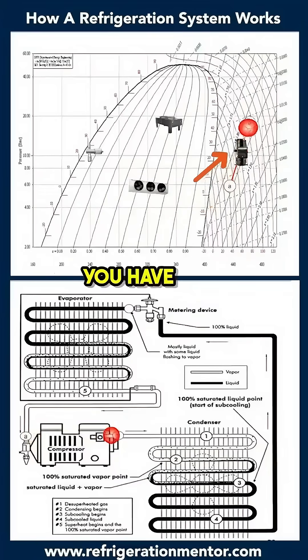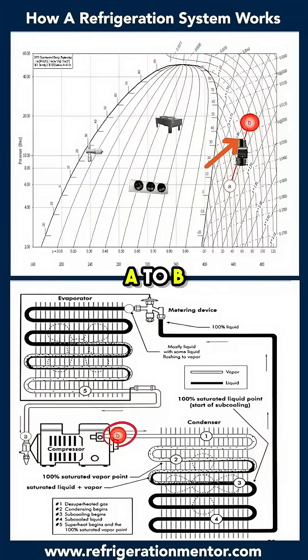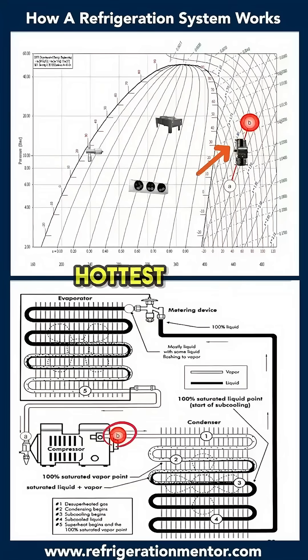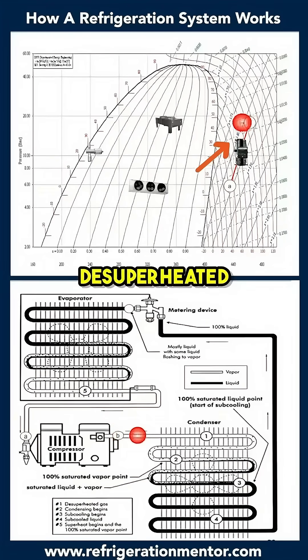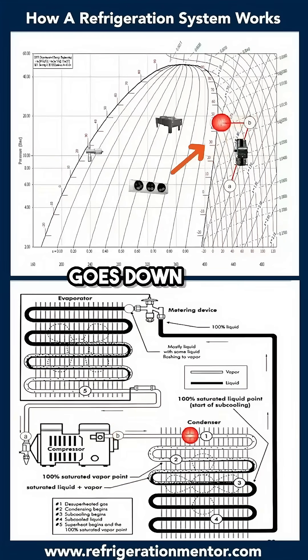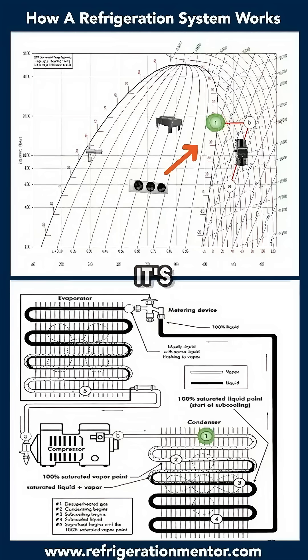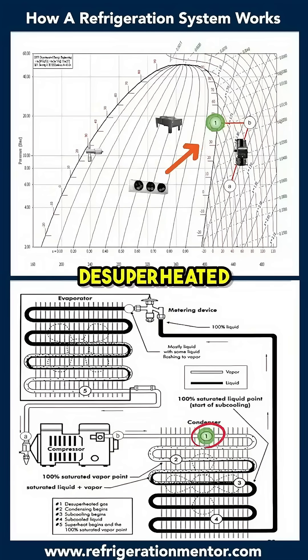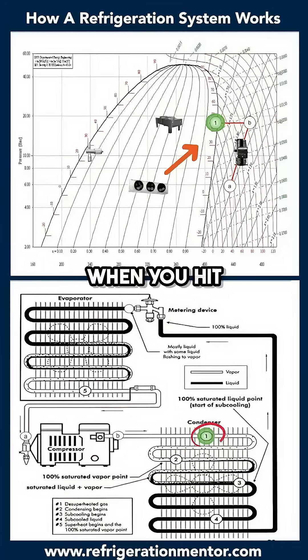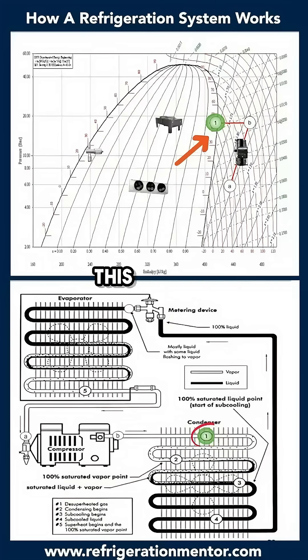As the compressor starts up, you have heat of compression — you go from A to B. At that discharge port, that's the hottest point. Anything past that is desuperheated, so as it goes down your discharge line it's a high-pressure, high-temperature gas being desuperheated on the way to the condenser.